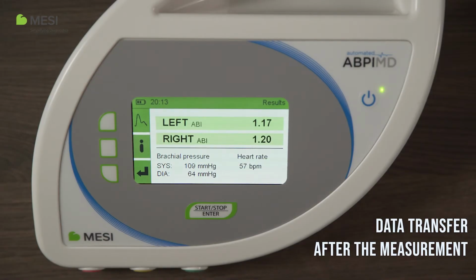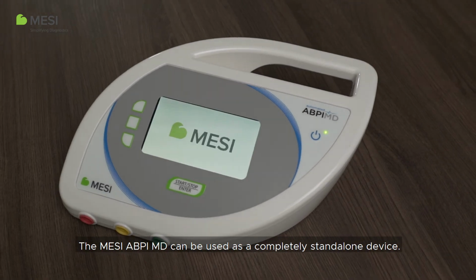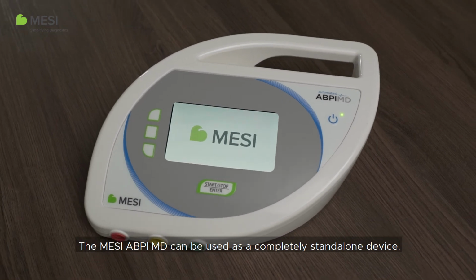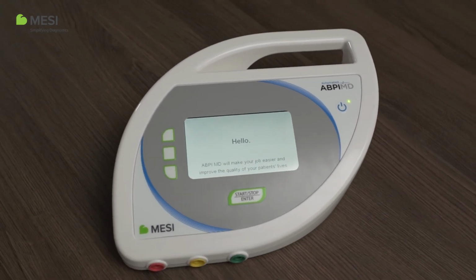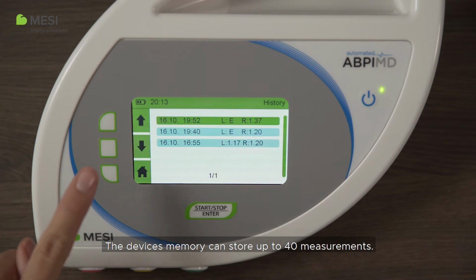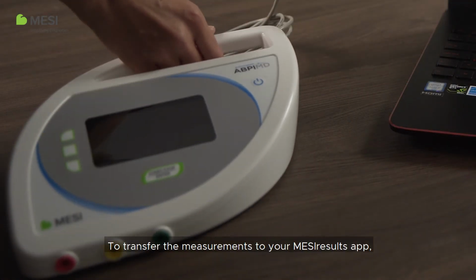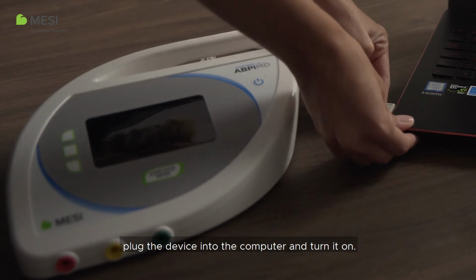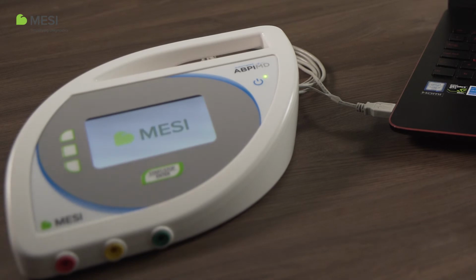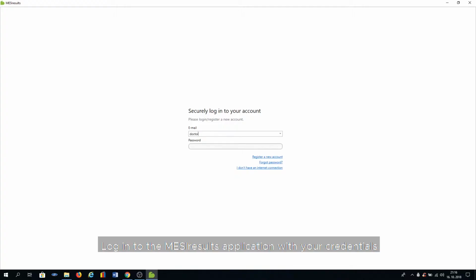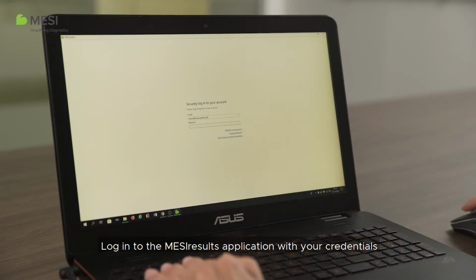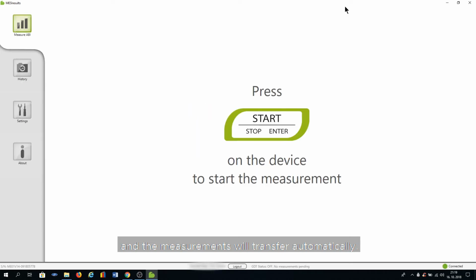Data transfer after the measurement. The MESI ABPI MD can be used as a completely standalone device. The device's memory can store up to 40 measurements. To transfer the measurements to your MESI Results app, plug the device into the computer and turn it on. Log in to the MESI Results application with your credentials and the measurements will transfer automatically.